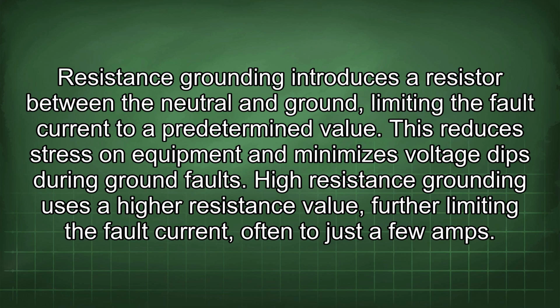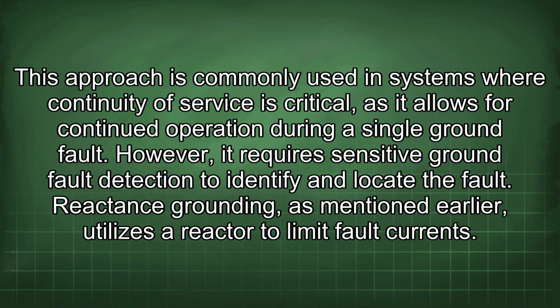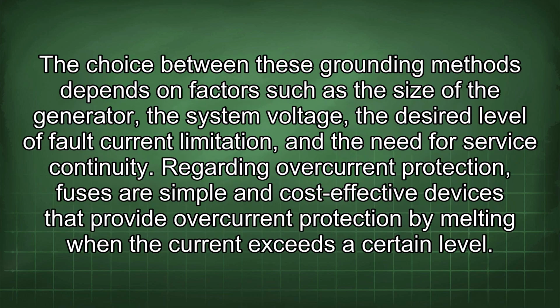High resistance grounding uses a higher resistance value, further limiting the fault current, often to just a few amps. This approach is commonly used in systems where continuity of service is critical, as it allows for continued operation during a single ground fault. However, it requires sensitive ground fault detection to identify and locate the fault. Reactance grounding, as mentioned earlier, utilizes a reactor to limit fault currents. The choice between these grounding methods depends on factors such as the size of the generator, the system voltage, the desired level of fault current limitation, and the need for service continuity.